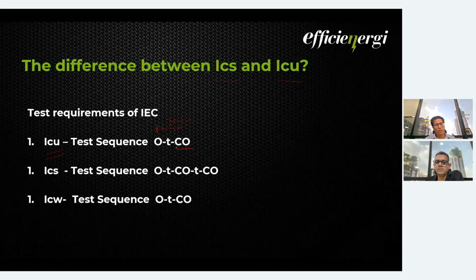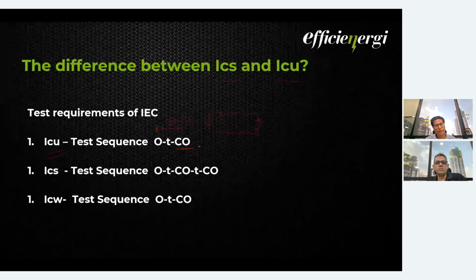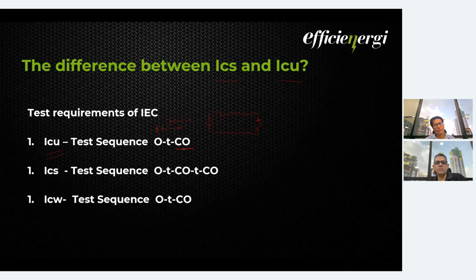So the fault circuit is already there, and you have the circuit breaker. You have to close it and immediately open it. After this test sequence, physical verification of the breaker is done. If there is no physical damage to the breaker, then ICU is passed.